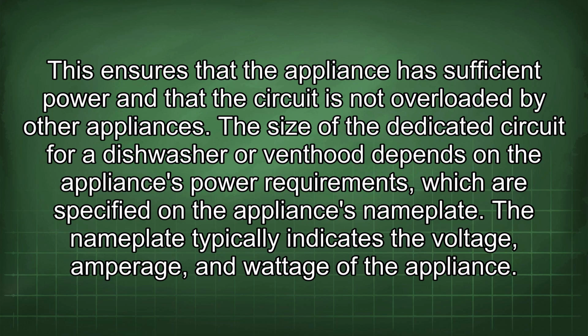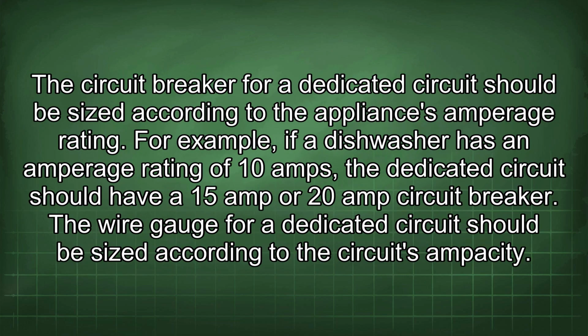The size of the dedicated circuit for a dishwasher or venthood depends on the appliance's power requirements, which are specified on the appliance's nameplate. The nameplate typically indicates the voltage, amperage, and wattage of the appliance. The circuit breaker for a dedicated circuit should be sized according to the appliance's amperage rating. For example, if a dishwasher has an amperage rating of 10 amps, the dedicated circuit should have a 15 amp or 20 amp circuit breaker.